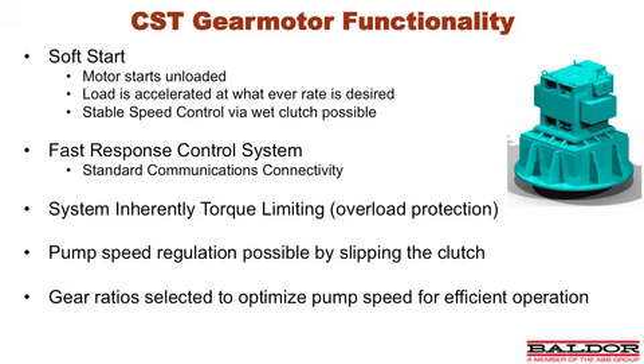A little bit on the CST gear motor functionality. It comprises a soft start, called an electromechanical soft start. This allows the motor to start unloaded. The load is then accelerated at whatever rate is desired, providing stable speed control via the wet clutch. We also provide a fast response control system with standard communications connectivity. The system is inherently torque limiting with overload protection, and pump speed regulation is possible by slipping that hydroviscous clutch. The gear ratio selected is based on optimizing the pump speed to provide efficient operation, meaning we will design the gearing to hit the optimum speed of the pump to achieve best efficiency point.